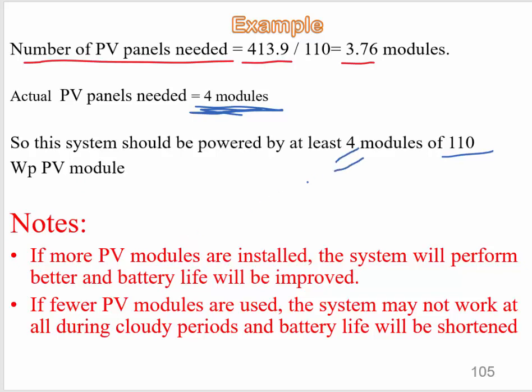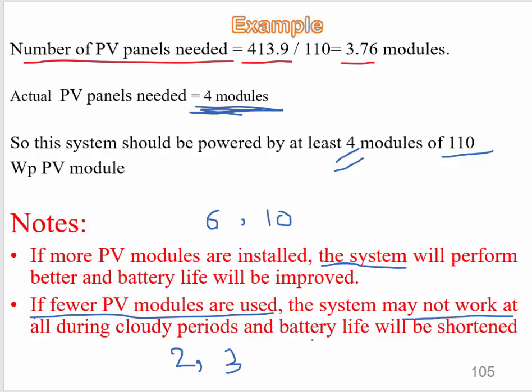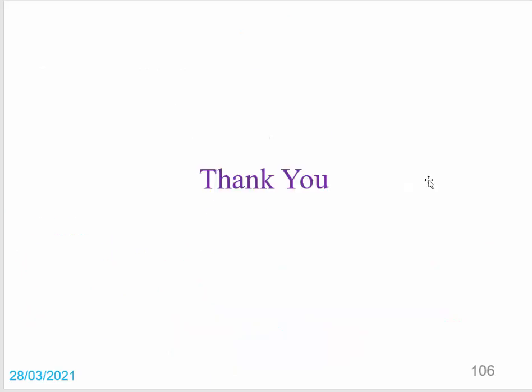Two additional notes: if more PV modules are installed — for example six or ten instead of four — the system will perform better and battery life will be improved, but cost will increase. If fewer modules are used — for example two or three — the system may not work at all during cloudy periods and battery life will be shortened. The optimal number for this system is four modules.